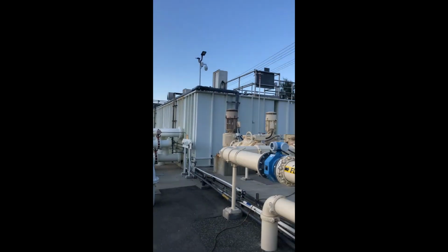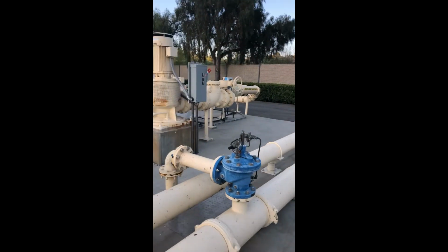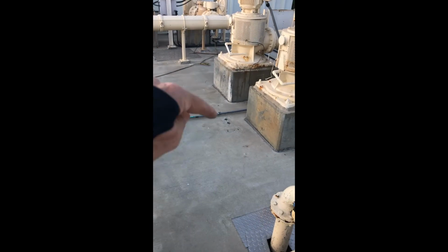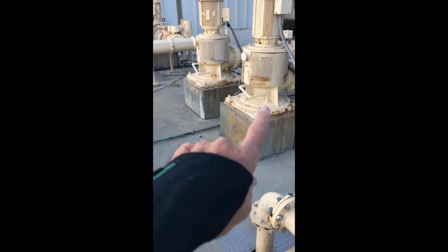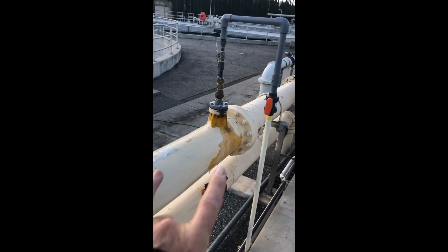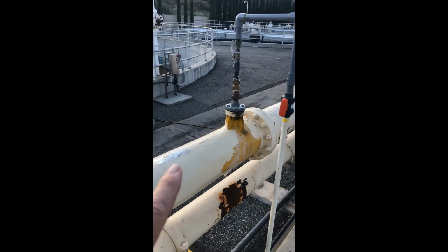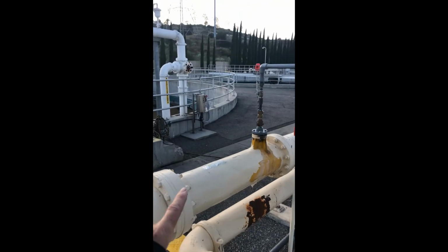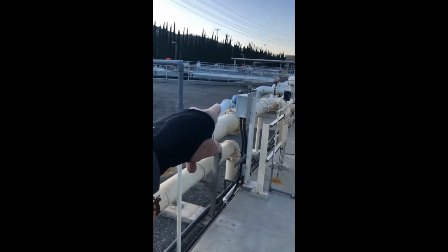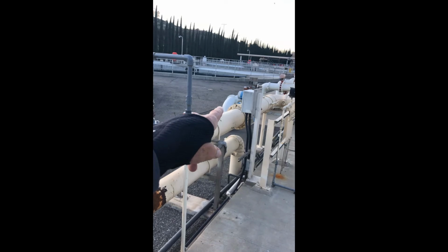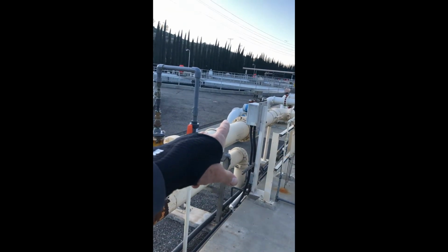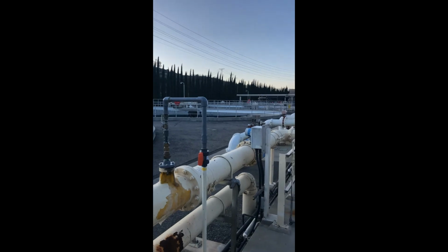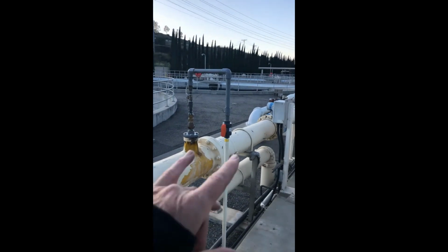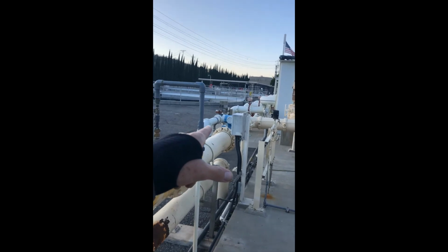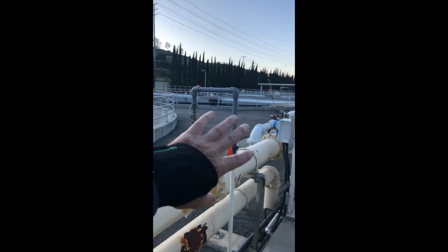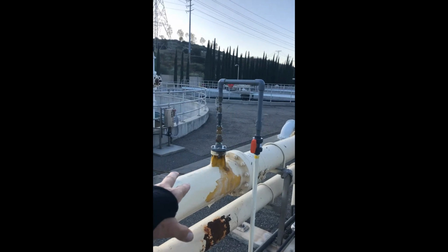Clean water comes out of the filters. It goes down into this wet well that's underground here. These pumps pull that clean water out, send it through this pipe right here. Bleach is added, okay? And the bleach is added proportionally to the amount of flow that that flow meter over there sees. And that's all controlled in the PLC. And that is going to be an open loop control. With that control, we just take a look at how much water is coming through the pipe, and we proportionally add enough bleach to get the chlorine residual that we want.